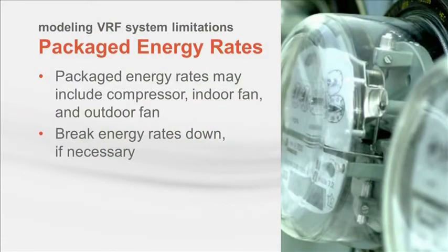Like any other equipment simulation, it's critical to enter correct energy rates for VRF equipment. With VRF equipment, the rates provided may be combined. This means that the compressor, condenser fans, and indoor fan powers may be summed and reported as a single energy rate. If the simulation program models the compressor, indoor fan, and outdoor fans independently, you may need to break the components out from a packaged rate and enter them separately.